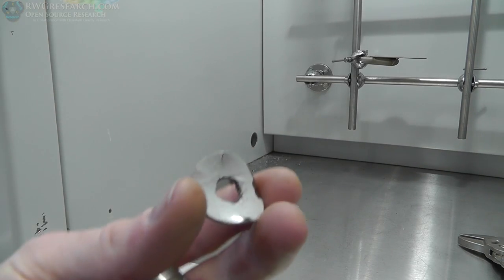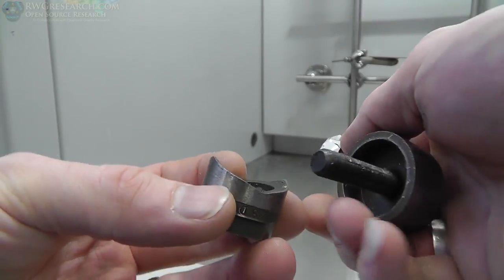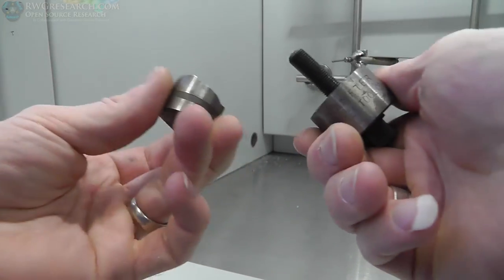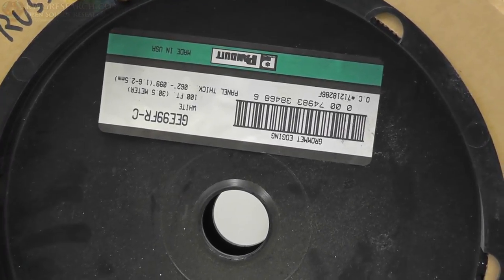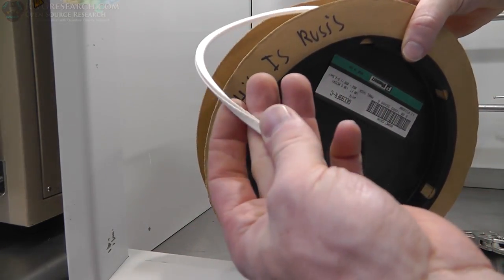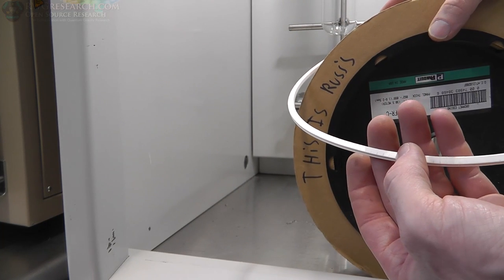Here we go. And that's how that's done. It is just that simple. Because there's a sharp point and then where it starts to work its way down, you don't have all that shear in one place to punch a hole. You work from a point and you work your way down. You have the paint flickering off. Easy as pie. In case you're wondering, I'm going to be using this, which is Panduit edge covering that I got from, actually believe it or not, I bought this at a yard sale. So it's a whole roll. Official Panduit. It's good stuff. This is what we're going to put on that edge so we don't have a sharp edge. It just fits on that edge. Pop it on there. Now we don't have a sharp edge. Perfect.